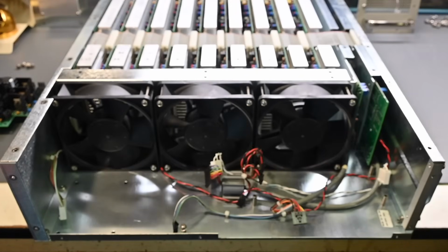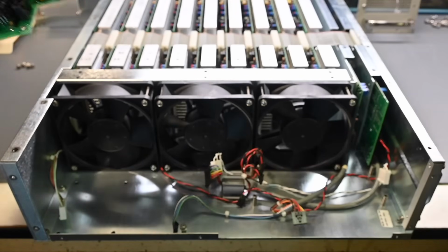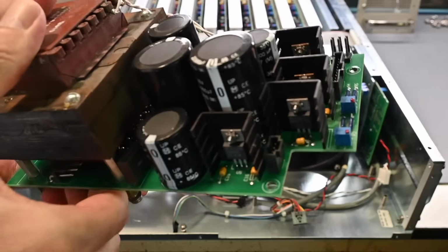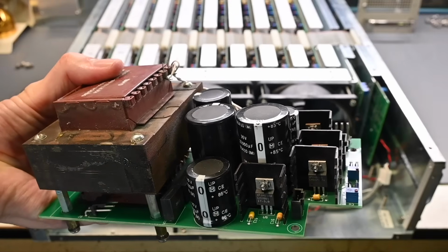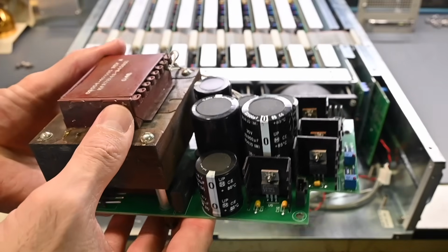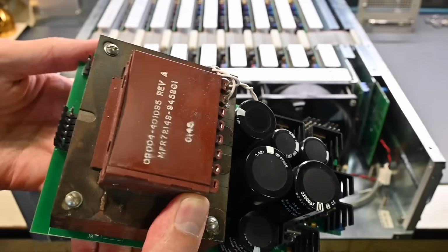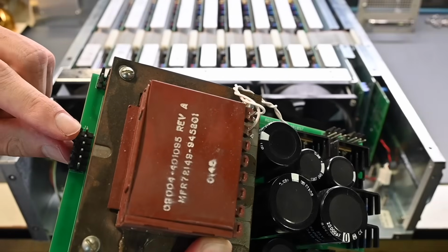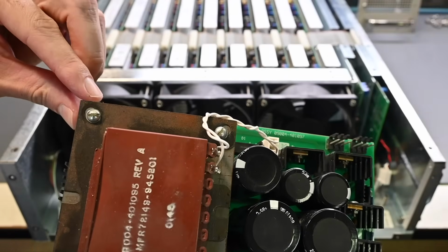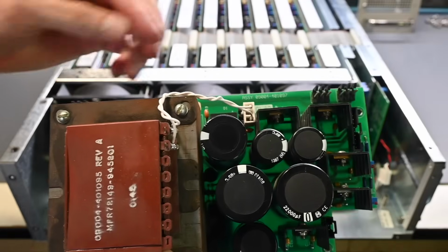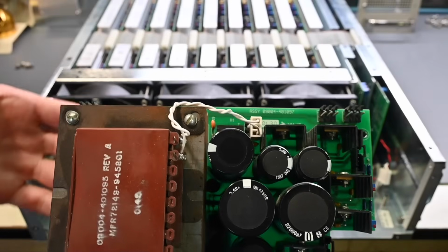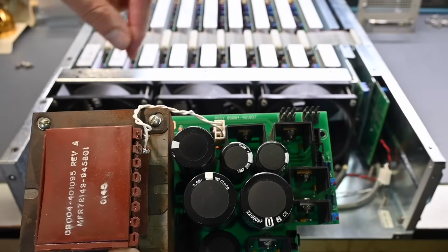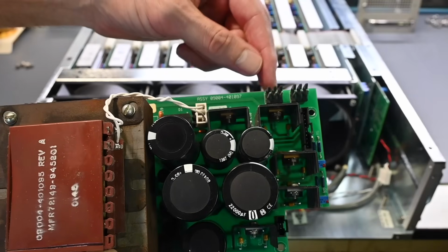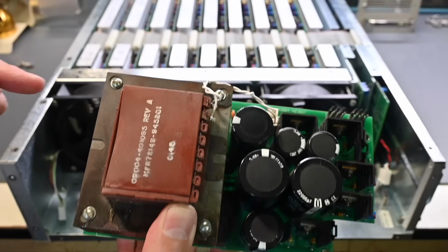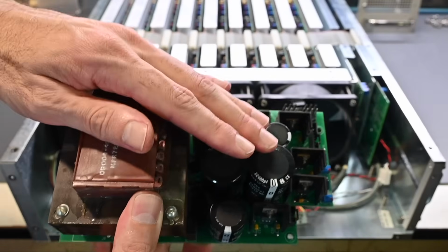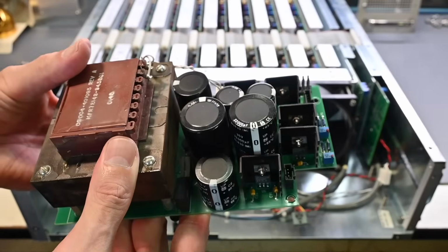And then over here is the second power supply. Very heavy transformer on this board. So this powers everything else in the electronic load. The AC line comes in this connector here, and this connector right there, and these connectors over here are AC pass-through, and the fan power supply we just saw is powered off of one of these connectors. So the AC line comes in, powers this transformer, and then continues on and powers the other transformer.